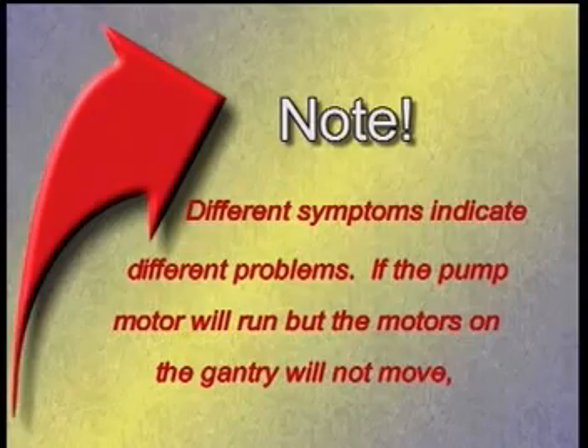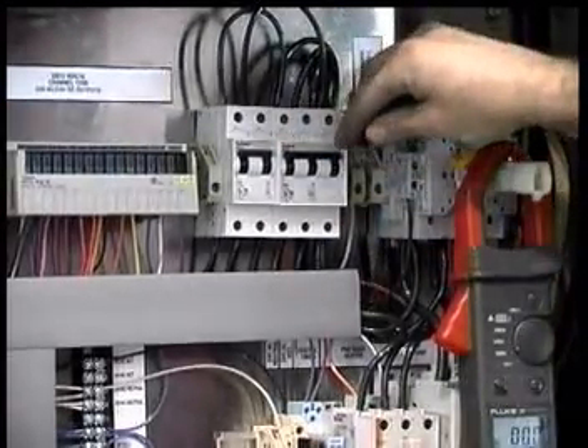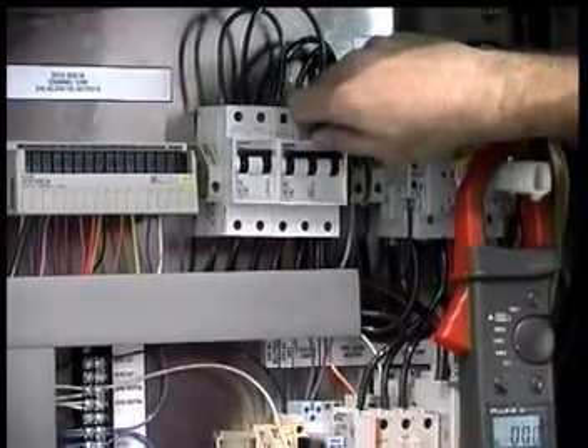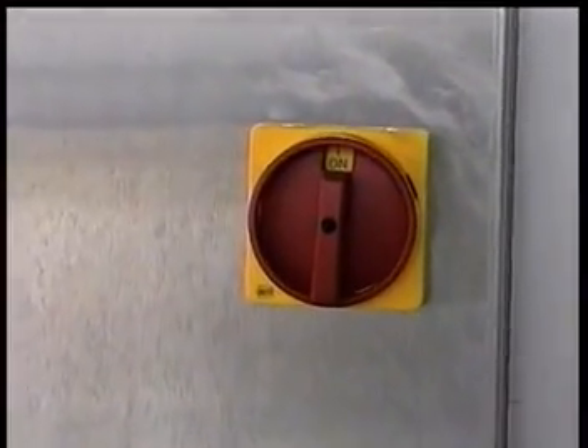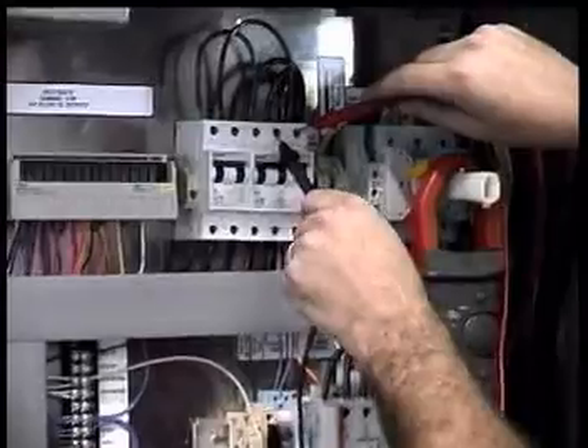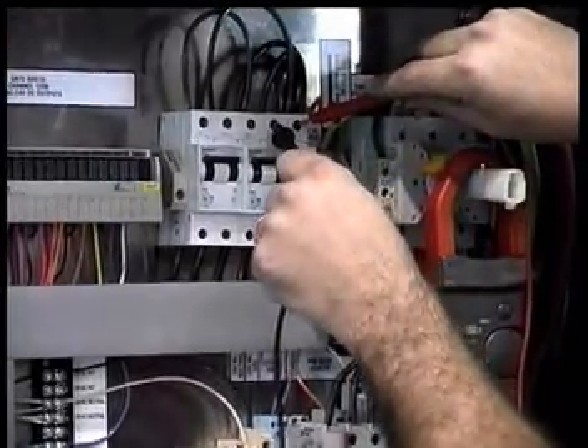If the pump motor will run but the motors on the gantry will not move, first check the 220 breaker in the control panel and that the gantry disconnect is in the on position. Then check for voltage on the top side of the breaker and then the bottom side.